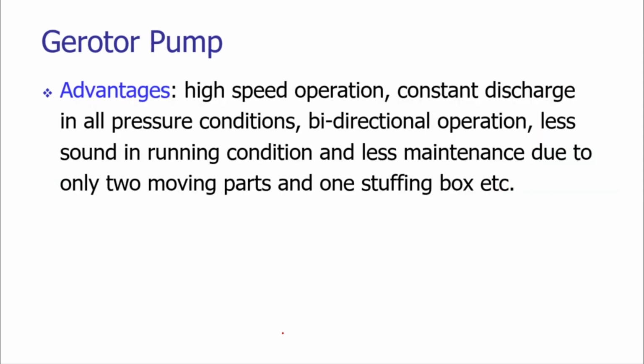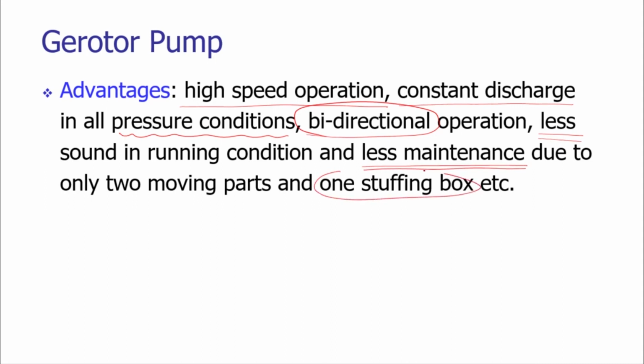Gerotor pump offers various advantages and these are on your screen. They are providing us high speed operation. They generate constant discharge in all pressure conditions. We can have the bidirectional operation, in a clockwise or anti-clockwise direction, we can easily carry out the operation. The sound is less and the maintenance is also less. The construction is compact, they are accommodated in a stuffing box.